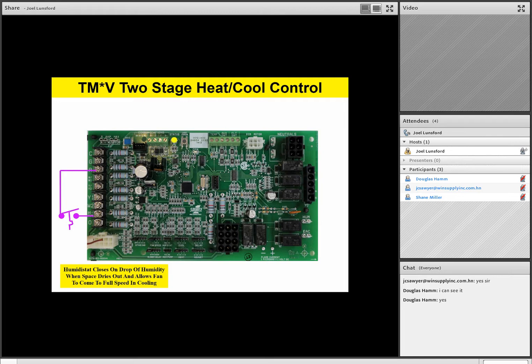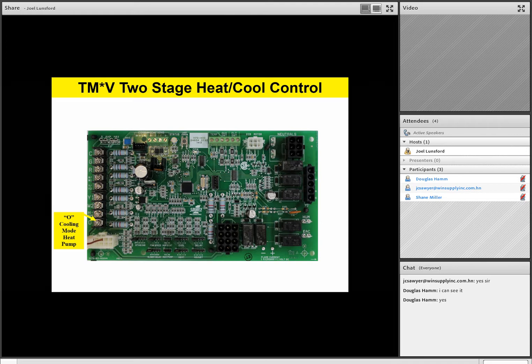Right below that, we have our O terminal for cooling mode of operation on a heat pump. If you have this hooked up in a dual fuel application, the O terminal will be energizing the reversing valve on the heat pump in the cooling mode. As you move up towards the top of the board, in the upper left-hand corner there's our 5 amp maximum fuse terminals. I don't know why I don't have a fuse in the picture, but that's where your low voltage fuse would go, up to 5 amp maximum.